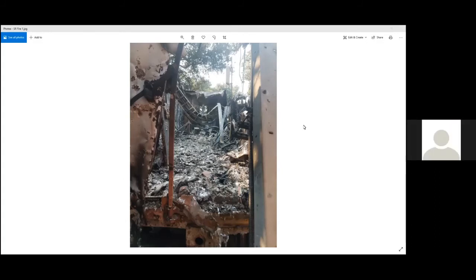I got called into a station at the Bay Bridge Toll Plaza about 6 o'clock in the evening. They'd gone off the air. I went out there and the lights in the building were going bright and dim, along with the tower lights. The transmitter was operating because it had 3-phase power, but there was no neutral in the building. When the tower lights came on, they unbalanced everything.